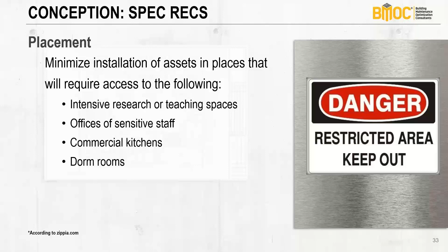What happens there is I almost always see residential and dining services replace the filters in those units semi-annually rather than quarterly when students aren't in the space, but they really do need to be replaced quarterly. It's difficult to do it mid-term when students are in the space. So one of the best systems I've been seeing lately is dorms with suite style setups, with an upright air handling unit accessed from a utility closet in the corridor, so they don't have to go inside the dorm room. Even better, I've seen systems with central chillers and boilers using chilled and hot water rather than refrigeration systems. Having a system accessed from the corridor rather than going into the room is ideal.